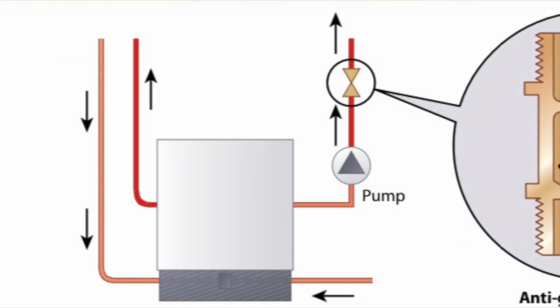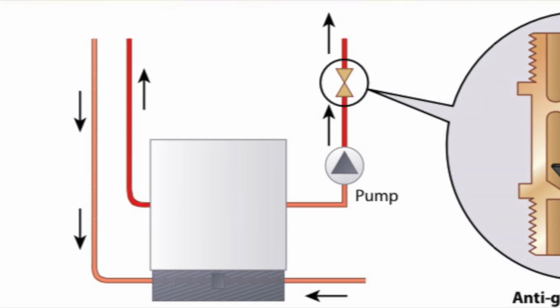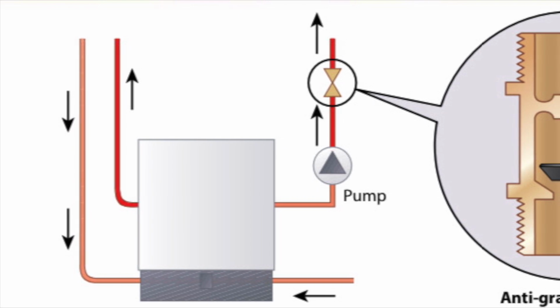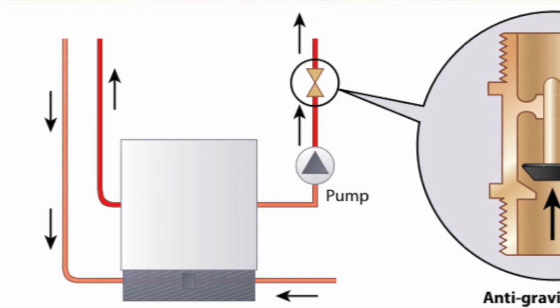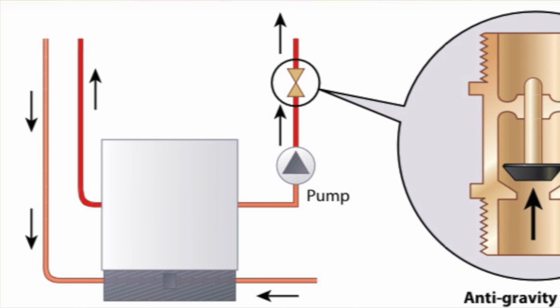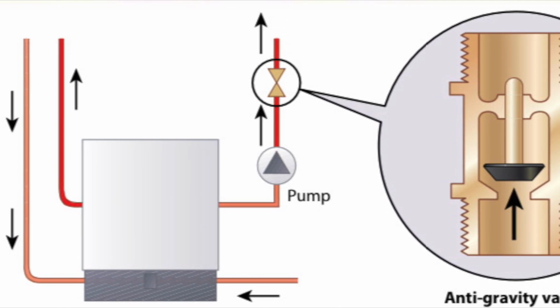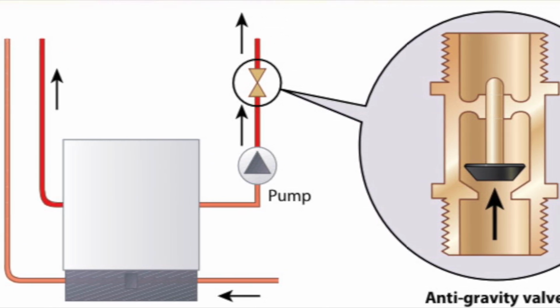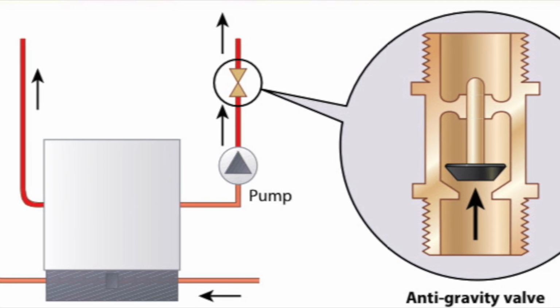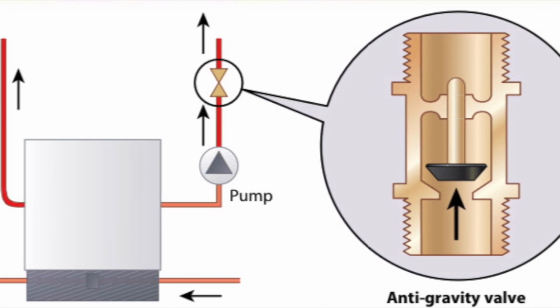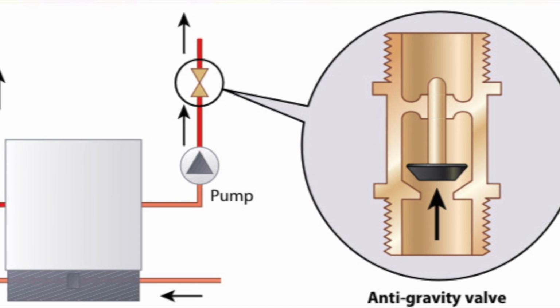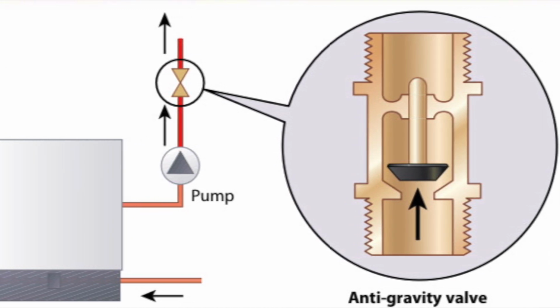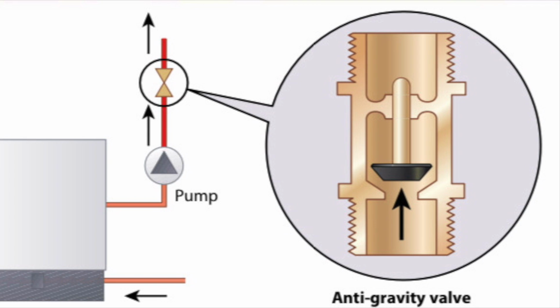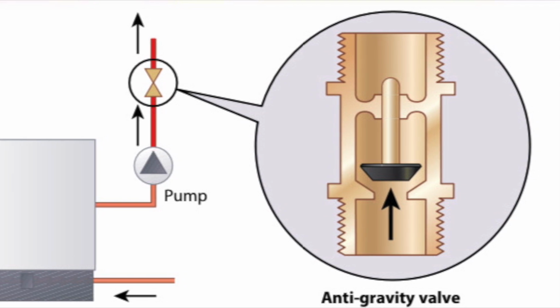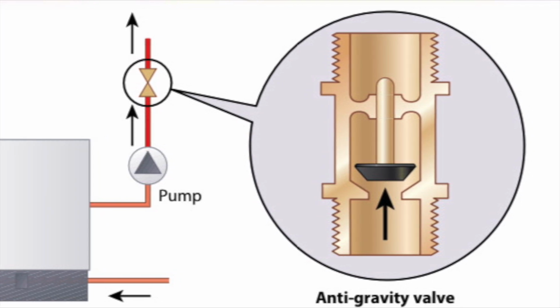So the way of telling whether this anti-gravity valve needs replacing is, there can often be excessive amounts of air in the radiators if the valve gets stuck open. The radiators can also get hot only when the hot water is being switched on. If the valve gets clogged up or stuck shut, then the water will not be able to circulate around the radiators when the heating is on, so your heating will stay cold. Again, it's as simple as that.